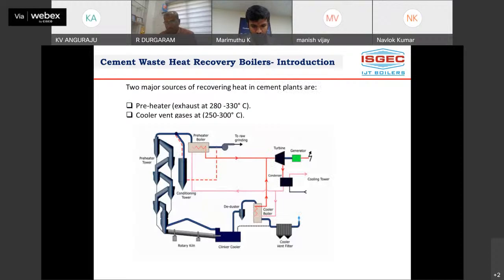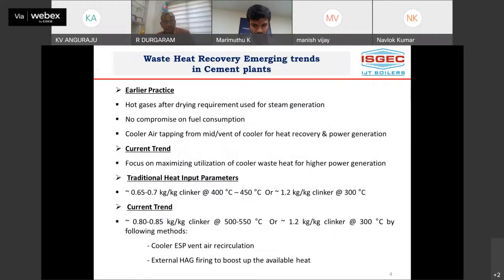Now, this is a diagram we've already seen in both presentations. From the preheater, we will be putting the preheater boiler. The preheater exhaust temperature ranges from 280 to 330 degrees centigrade, whereas the cooler vent gases are 250 to 300. Nowadays, with various mid conditions, the temperature goes even up to 600 degrees centigrade as a maximum. A few plants operate at very high temperatures based on the tapping location.